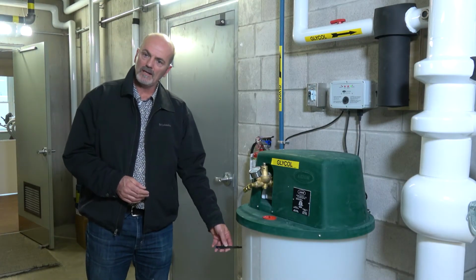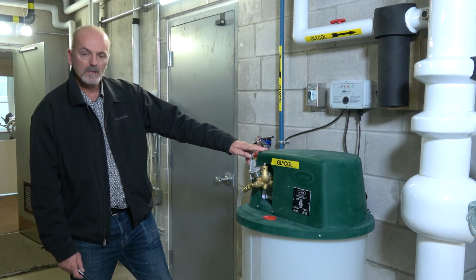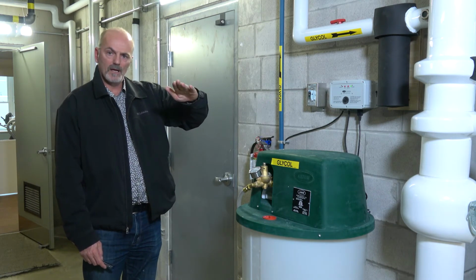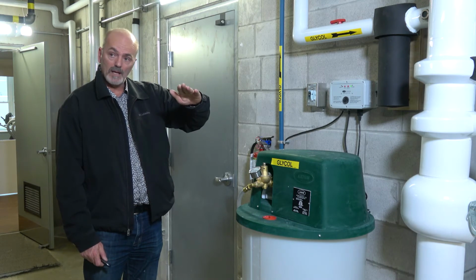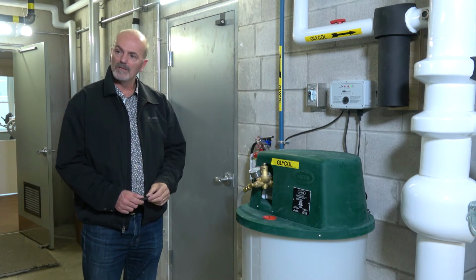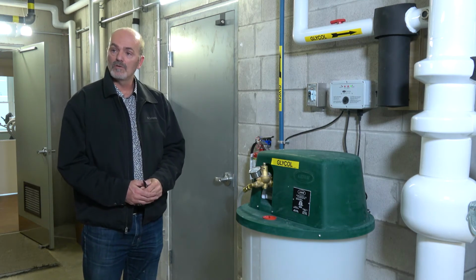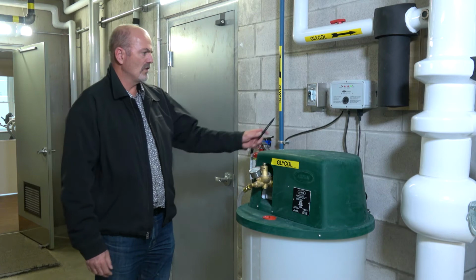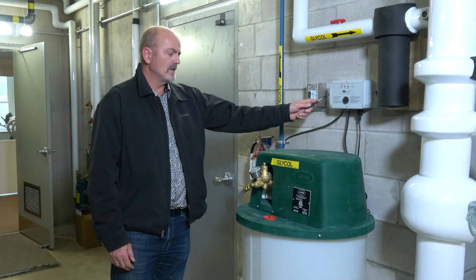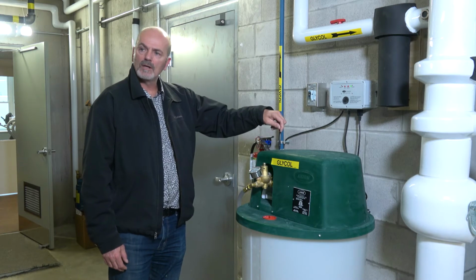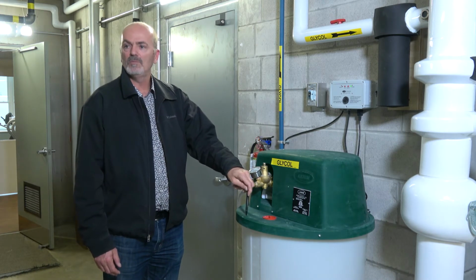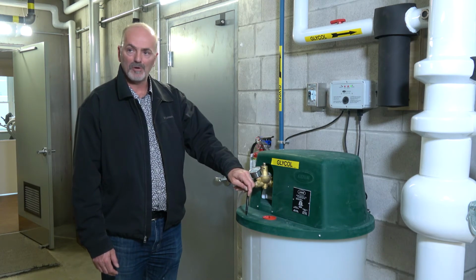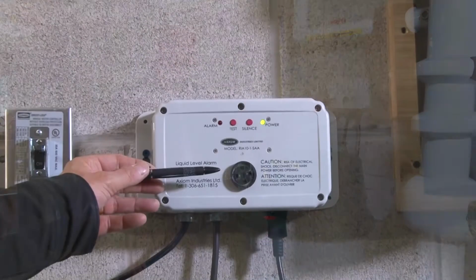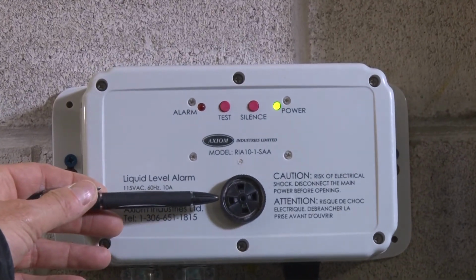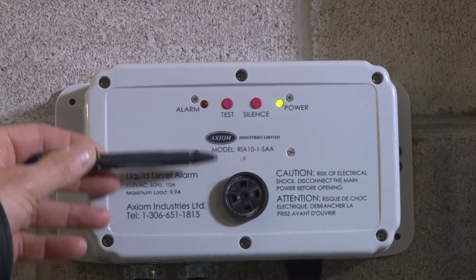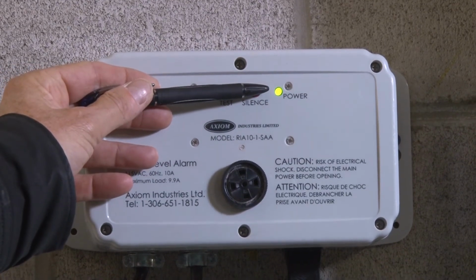And it will automatically do that. There is a float switch in the tank, so when the tank gets down very low, and the float switch changes from an angle, it's an angle float switch, so if it starts to drop, it will open its contact and will not allow the unit to run anymore. And in this case, they've incorporated a panel that's wired to the device, and the alarm contacts on the device say, hey, our tank is empty. We don't want our pump running anymore. We can't pressurize the system anymore. So it will activate the alarm, okay? And the alarm light will come on and the green status light will go off.